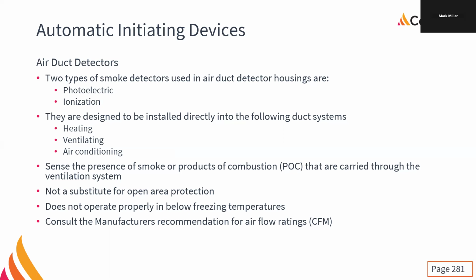And they do not like the cold. Just like any smoke detectors, they do not like the cold, which is a huge annoyance because so often we have to put them up on the roof because the ductwork's being run along the roof. It's really frustrating because now we have to put an insulated box in. Most of the manufacturers say that, oh yeah, you use this insulated box, it'll get the waste heat from the ductwork and it'll work just fine. Yeah, rarely happens. Often I end up putting in a little 20 watt, maybe a 40 or 50-watt heater.